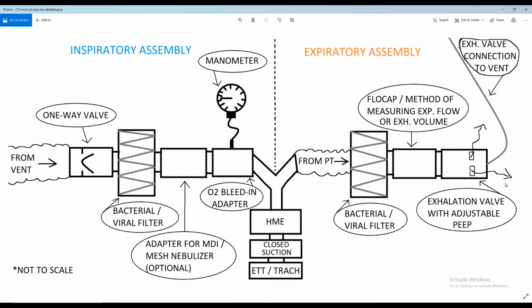So this little gray line here, that's just the connection that goes back to the ventilator that drives the exhalation valve. We would dial that up to whatever PEEP level we wanted, because our patients are obviously going to need some increased levels of PEEP to keep them from de-recruiting and keep their oxygenation up. So we would be able to potentially adjust the PEEP levels on a patient-to-patient basis, and whatever driving pressure is coming from the machine would stay the same, and you could manipulate your PEEP level with the valve right here.